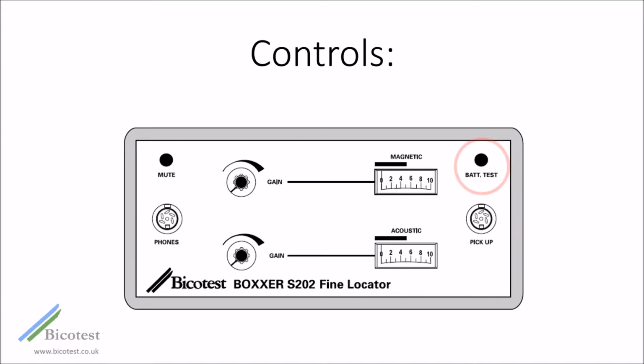Battery test button. This red push button switch is for checking the condition of the batteries as indicated on the associated meter. The gain control. There are two of these, one for each amplifier. Rotate clockwise to increase gain. Display meters. Two output display meters scaled 0 to 10. One for the acoustic channel, the other for the magnetic channel as marked. These give a proportional signal level indication for their respective channels.